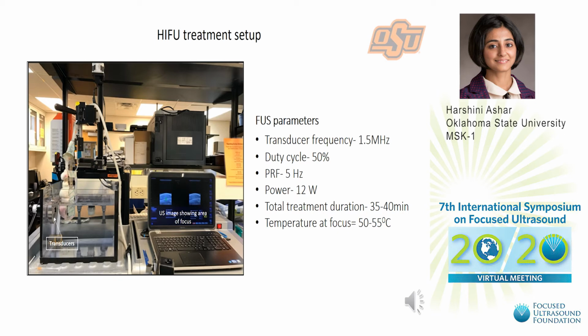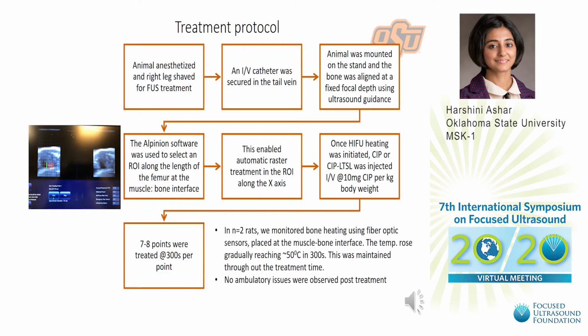We used 50% duty cycle, 5 Hz PRF, and a power of 12 watts, which generated about 50 to 55 degrees Celsius at the focus, and the total treatment time was about 40 minutes. So this is the general flow of the treatment.